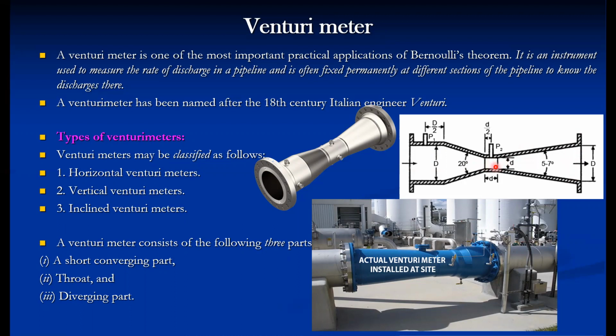So to avoid that, while designing a venturimeter, care has to be taken, especially for a volatile fluid like petrol. If we have to design a venturimeter for petrol flow, then care must be taken that the pressure here does not fall below the vapor pressure of the petrol. So this is the brief introduction to the venturimeter.